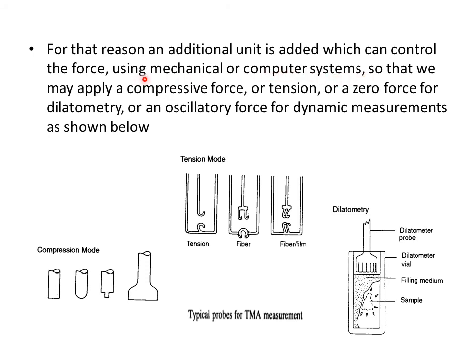This can be done mechanically or through software, so that we may apply a compressive force or tension, or even a zero force for dilatometry, or an oscillatory force if we are working with dynamic measurements. So all of these things are now possible mechanically, or even by using the computer system.